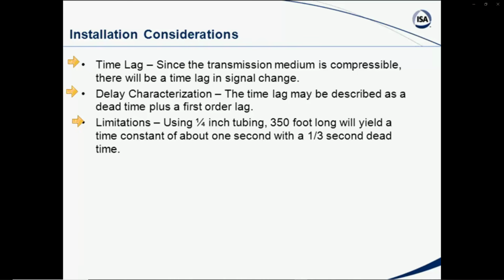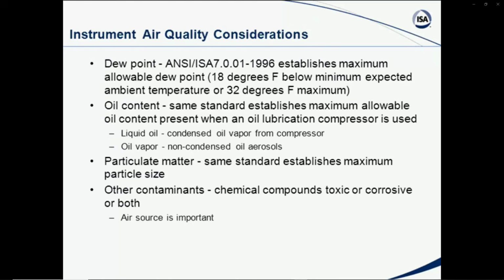And then there are some limitations. For instance, some tests run used 1/4 inch tubing, 350 foot long. They had a time constant of about 1 second, and actually had a 1/3 second dead time from the time they initiated a pressure change till it was actually received and impacted. So I think it's something that we need to be aware of, that pneumatics do exist. We wanted to cover that in this part of the seminar.